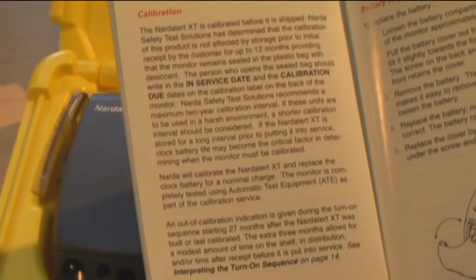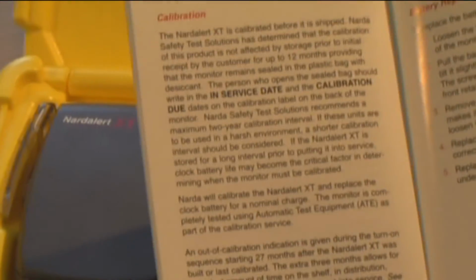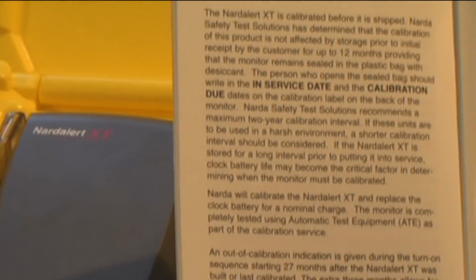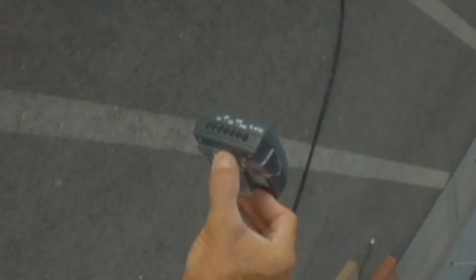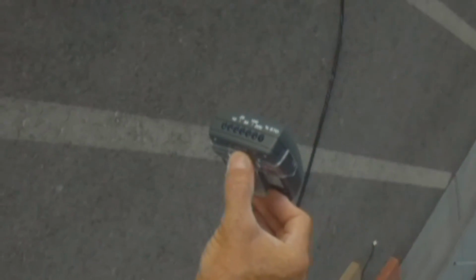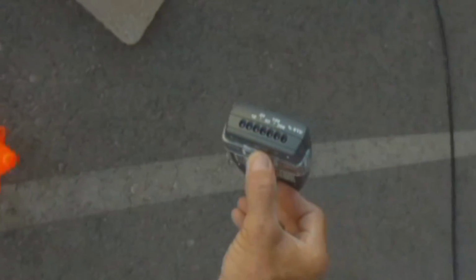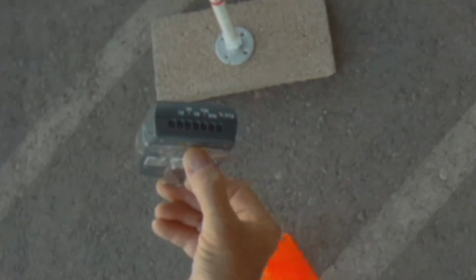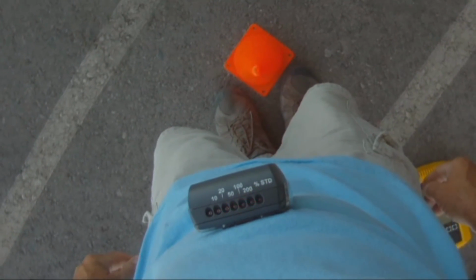It has a 2-year calibration cycle, but the calibration certificate does not include a traceable standard. This unit passed every accuracy test over our test frequency range, except for handheld use at low frequency. The unit was not designed for handheld use, and it was still very close to the plus or minus 6 dB limit. Since it works on the body at that frequency, we gave this unit a passing grade.